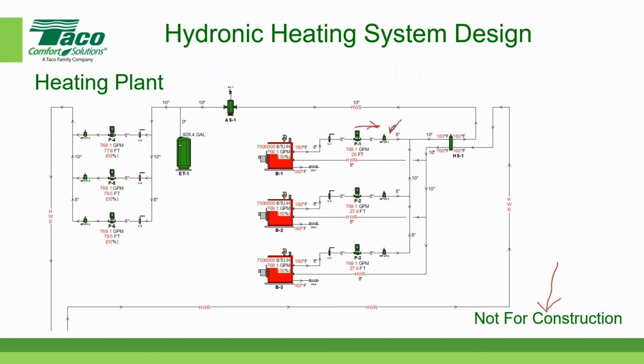And I also have, for balancing purposes, in this particular design, by the way, it's a constant flow on the primary side. In other words, I never change the flow. In this case, roughly 769 gallons per minute. And as long as that boiler is operational and that pump is running, it's going to run at a constant flow for the primary side. And the circuit for the primary side is down here into the hydraulic separator, comes back out, goes into the individual boilers as it flows back in each case. Comes down here. And then it feeds back. There's one boiler, then picks up the second boiler, there's two boilers, and then when it comes back here, we have all three boilers going into the hydraulic separator.